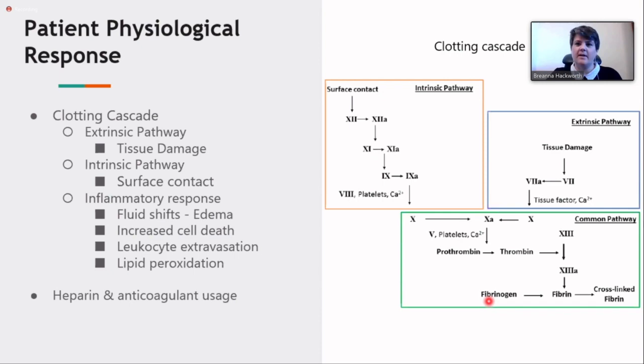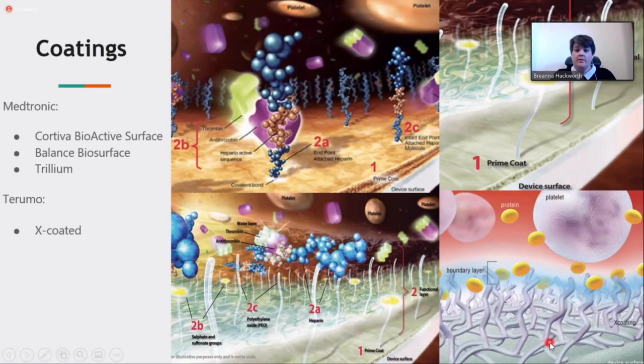The coatings that we looked at—we looked at four different ones, three by Medtronic and one by Terumo. In the upper left-hand corner, we have Cortiva bioactive surface. This is a heparin-coated surface, and it alternates anionic and cationic polymers, providing that thromboresistance. Next to that, in the upper right-hand corner, is balanced biosurface. This is a non-heparin coating surface that uses hydrophilic polymers.